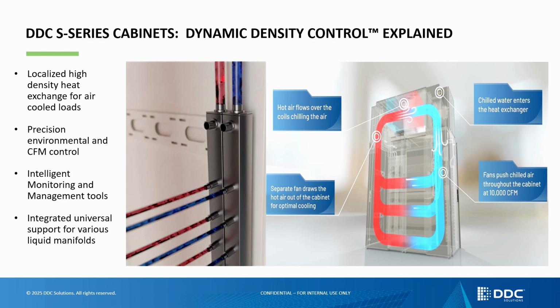The air side of the cabinet can produce up to 12,000 CFM of air, and at about 120 CFM per kilowatt, that's how you get to that 100 kW of cooling. Very, very difficult to do, but we've spent the last 10 years figuring it out, and it works flawlessly.